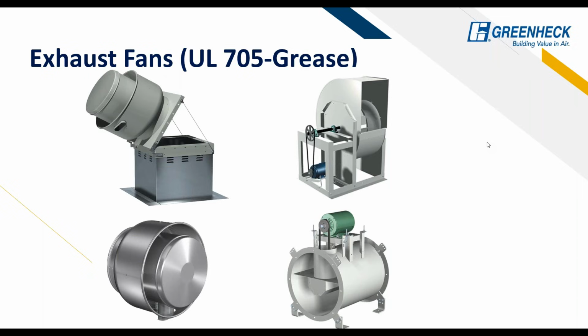Okay, so getting into exhaust fans, all the exhaust fans need to be listed with UL 705 grease. You might still see reference to UL 762, like I mentioned. Each fan will also need a hinge kit on the curb. If you're looking at an upblast fan, you will have a hinge kit. You'll have a grease cup. It's not shown here, but it'll be right there. All these fans are required to have a grease containment option as well.